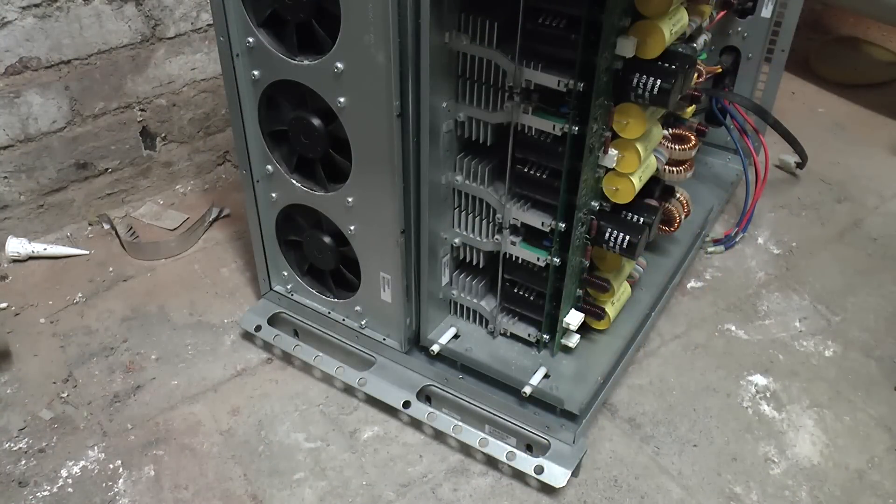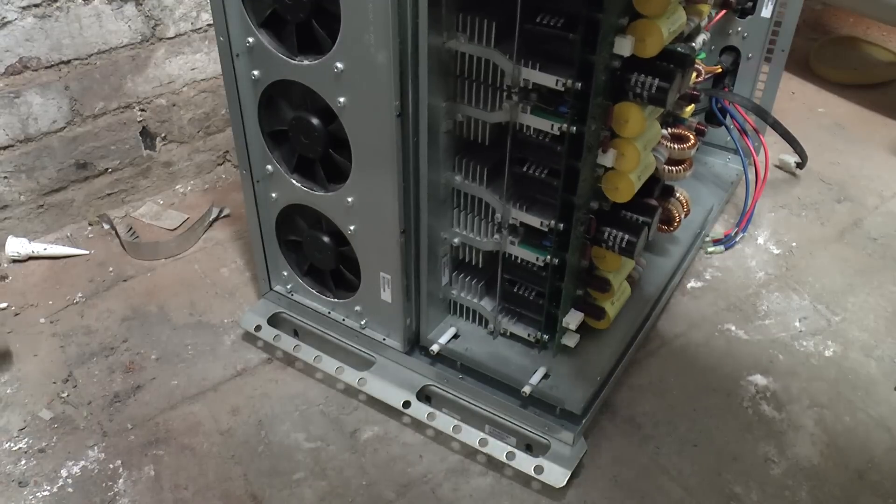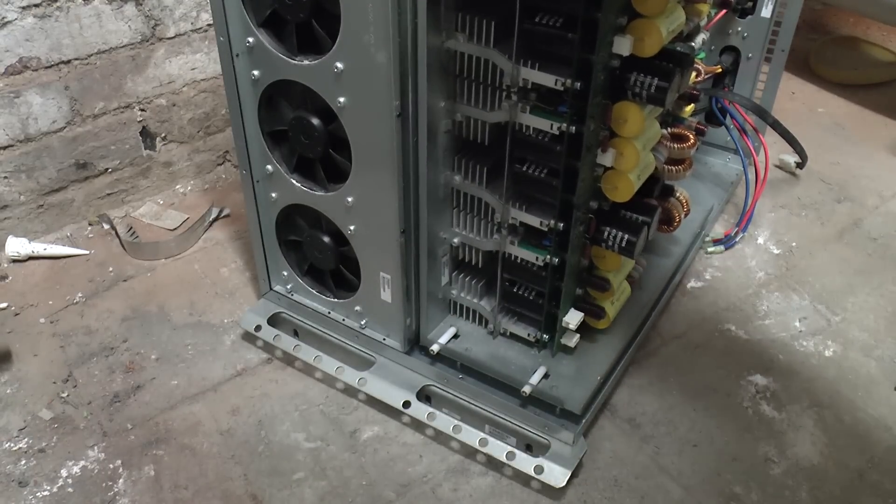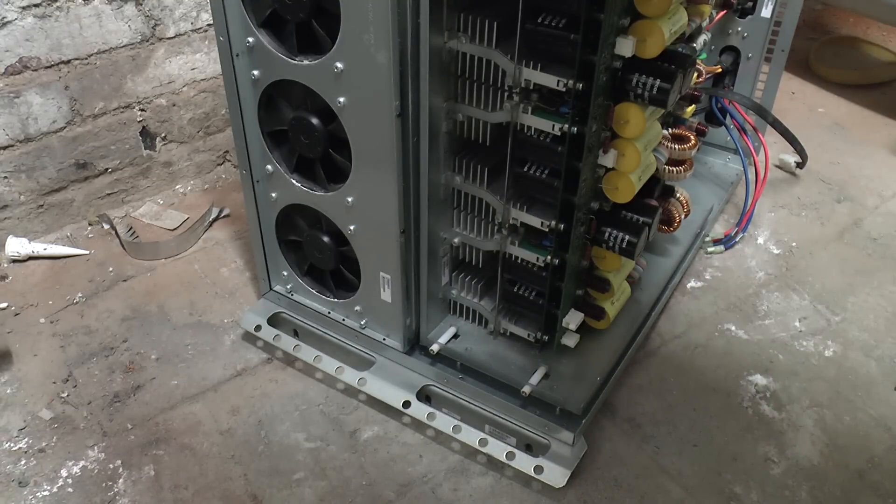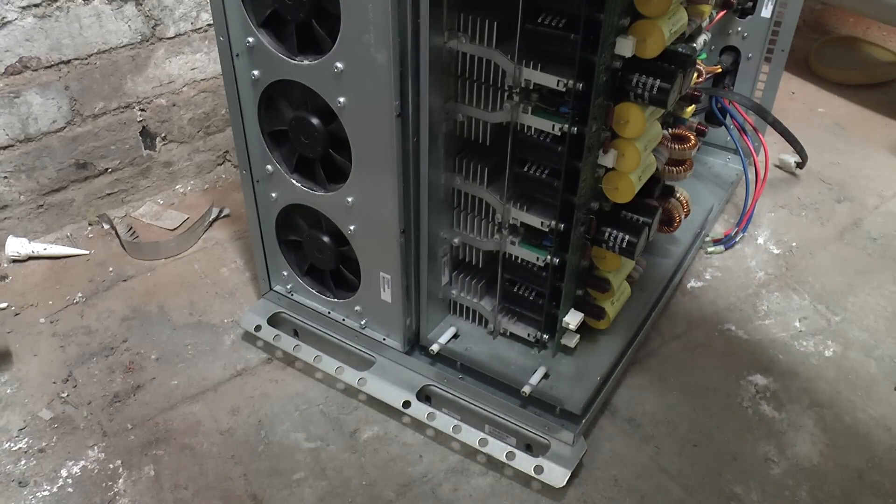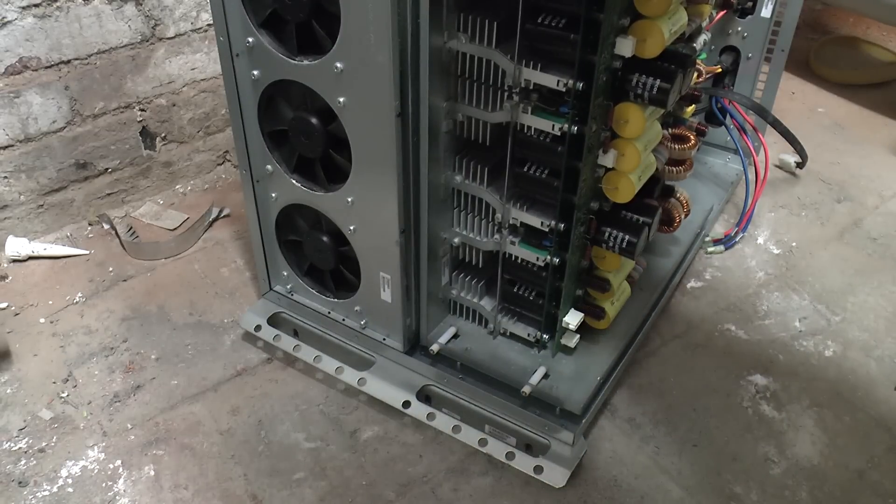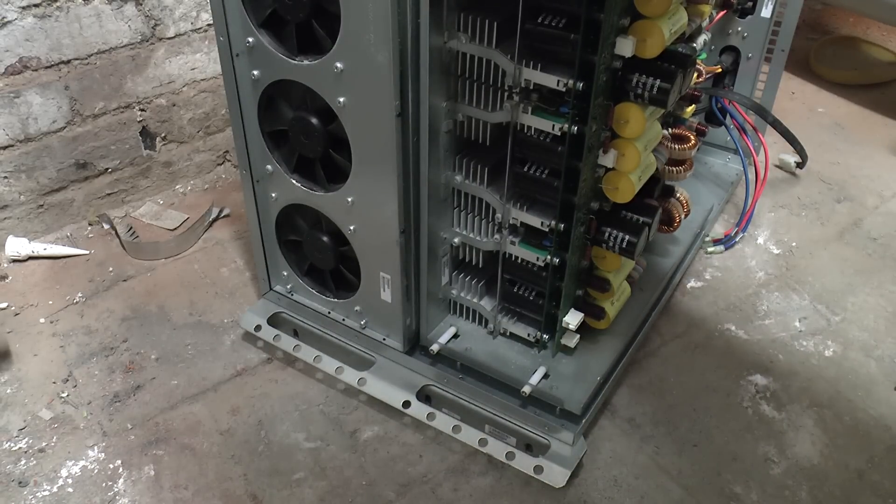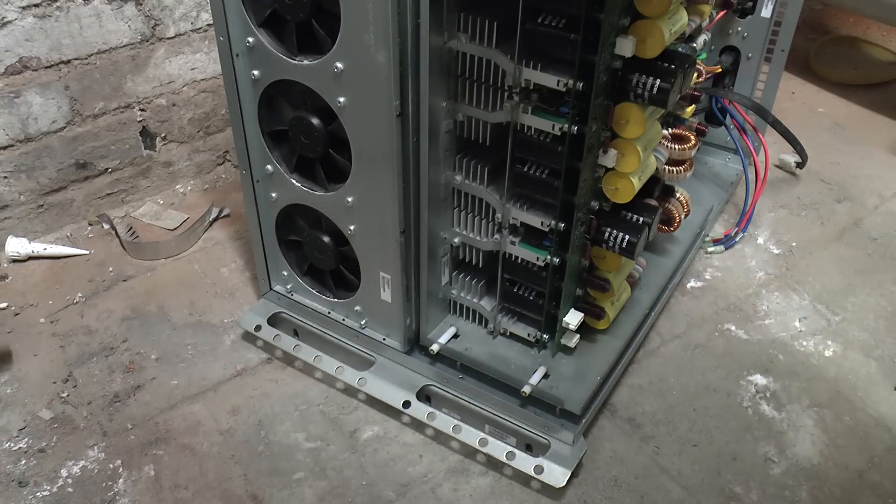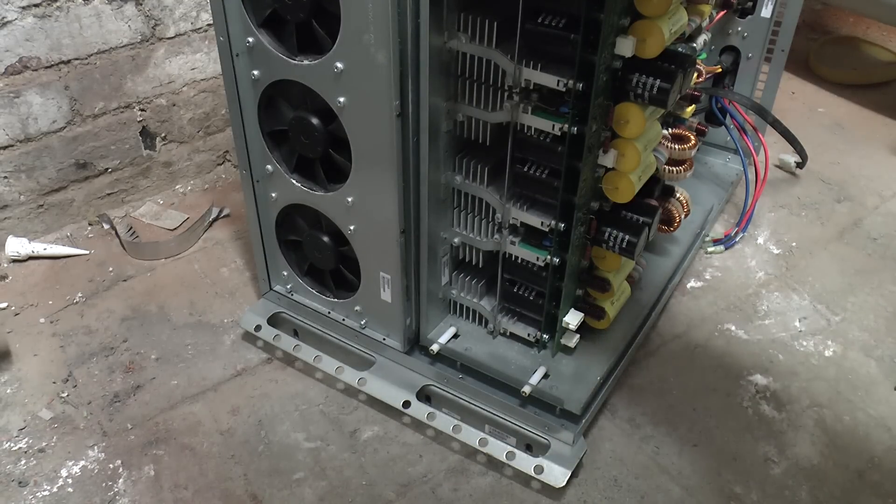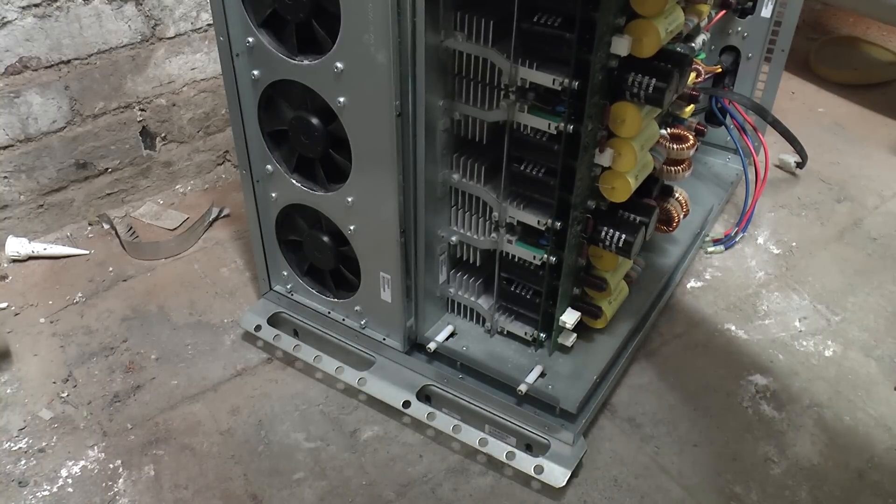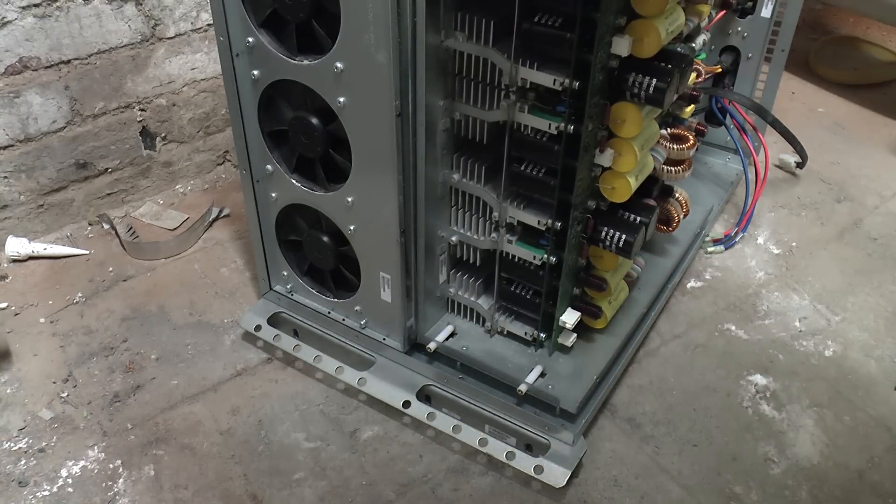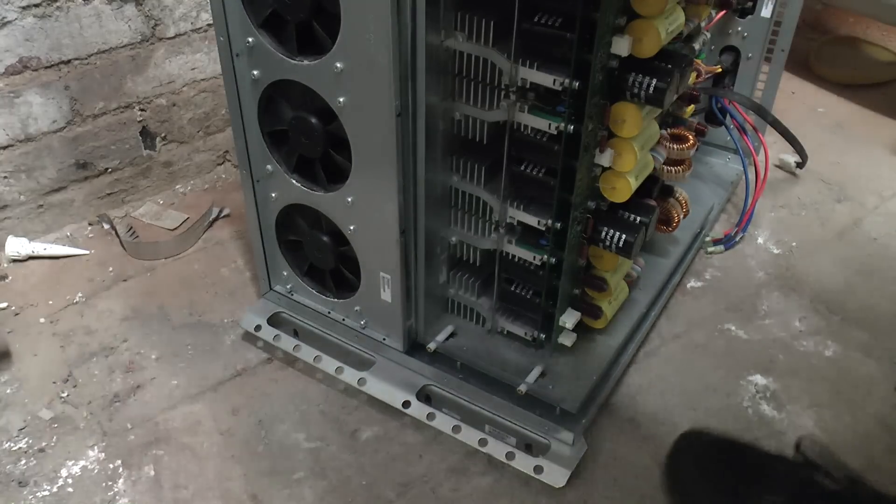An interesting part of the design here, as you can see, all this metal work is not in contact with the chassis. It's all spaced out. It sits on a metal plate which sits on a plastic spacer. The circuit board on the top wasn't connected directly to it either. It's all separated out. So presumably a fault in here could be detected and it shut down rather than faulting straight to earth. All the bolts out. That's a power module.